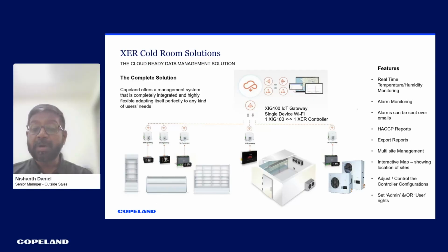In this slide, we see how the IoT gateway for these controllers can be implemented. It is not limited to the XER controllers; any prime controllers of Copeland can be connected via this IoT gateway for real-time monitoring of the solutions. It facilitates real-time monitoring and alarm monitoring. Remote monitoring and diagnostics allow for real-time adjustments and proactive maintenance. This means that the temperatures to be maintained for a cold room can be set onto the controllers, and any increase or decrease in temperature will result in alarms, either as emails to the people or as SMS or text messages.